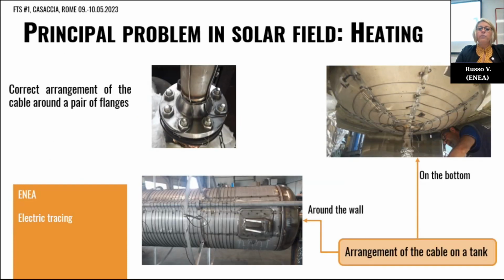Finally, here we have some pictures that show the correct arrangement of the cable on the tank. In this case, we have to install the electric cable both around the wall of the tank and on the bottom of the tank. And here instead there is a picture of the installation of the heating cable on a flange, because we know that the flange is a component that has high thermal losses. So we have to put the cable very carefully.